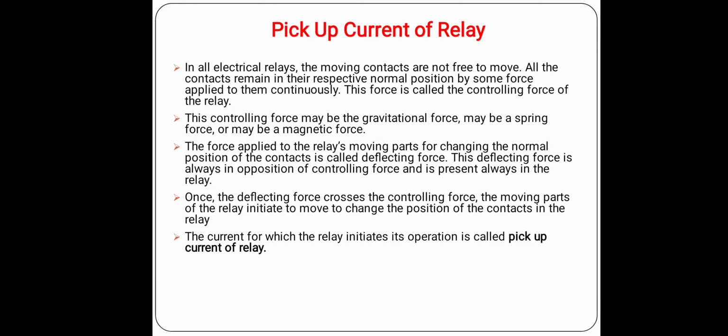If I elaborate on this, in all electrical relays the moving contacts are not free to move, and all the contacts remain in their normal position by some force applied to them continuously. This force is called the controlling force of the relay, and it may be gravitational force, spring force, or magnetic force. The force applied to the relay's moving parts for changing the normal position of the contacts is called deflecting force. This deflecting force is always in opposition to the controlling force and is always present in the relay.